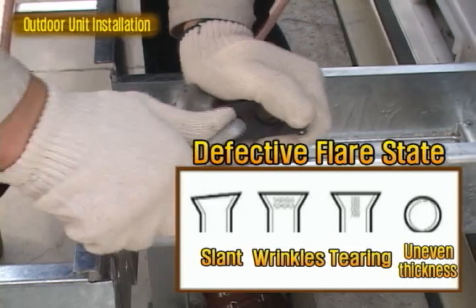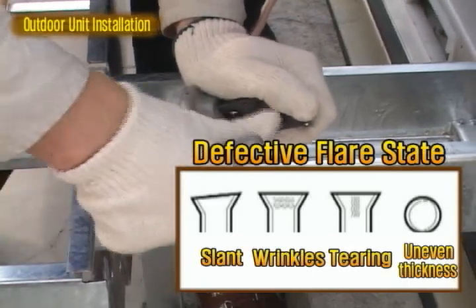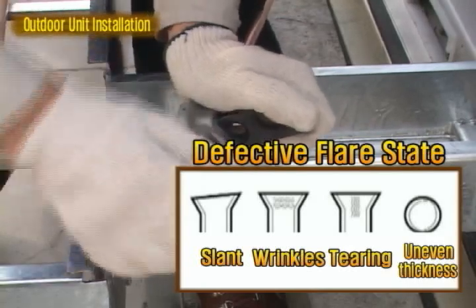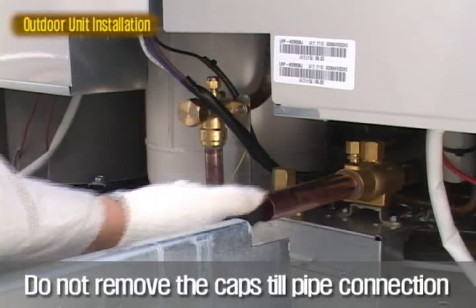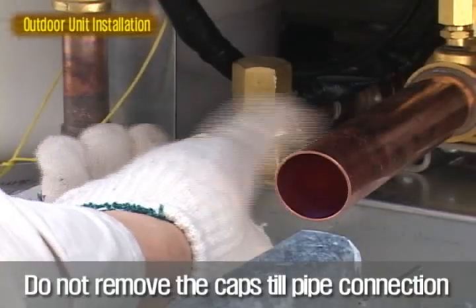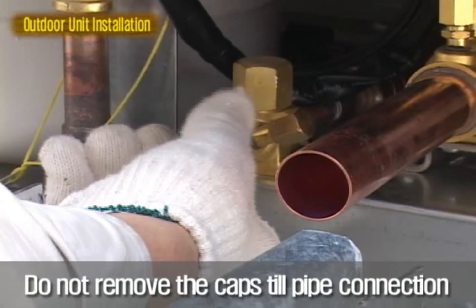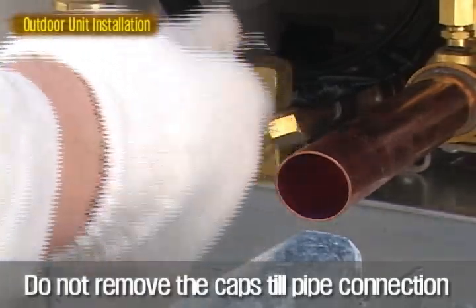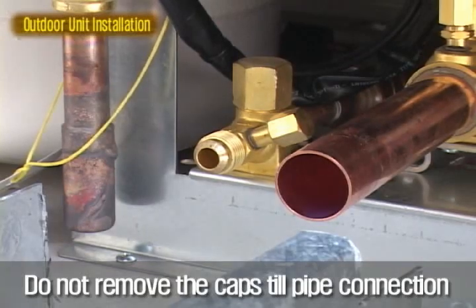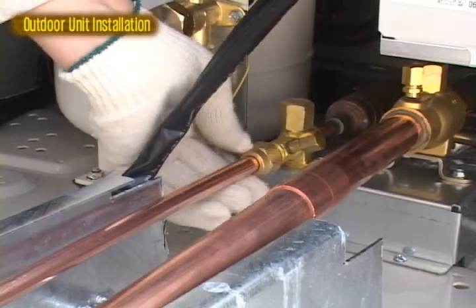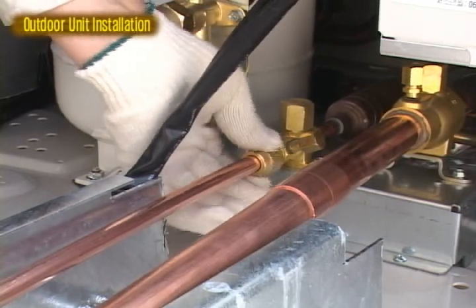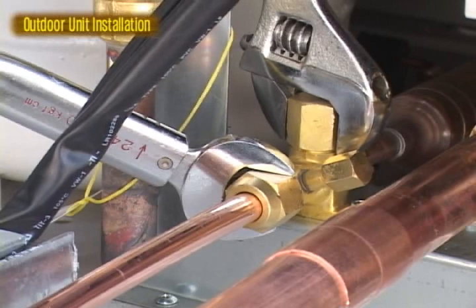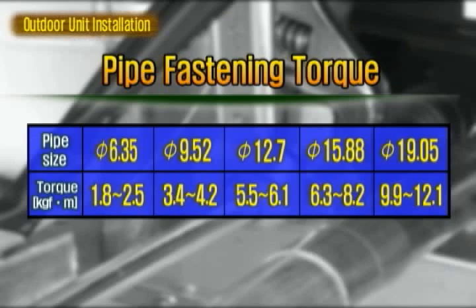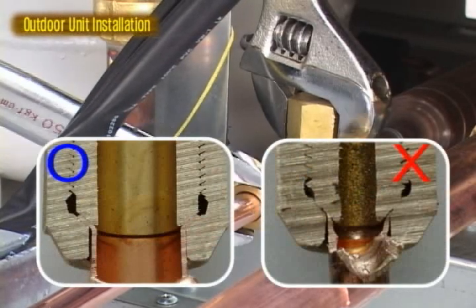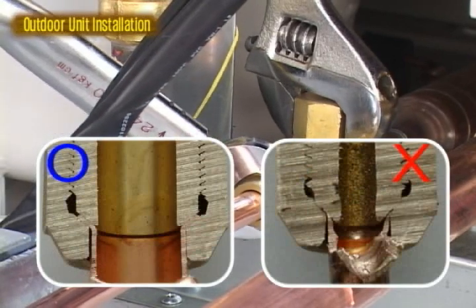Flare contact should be tight and accurate, otherwise leakage problems can occur from the flared part. Do not remove the nut and cap from the service valve and tube until just before the fitting. Earlier removal will cause troubles like allowing foreign materials into the pipes. Line up the branch distributor unit socket and flare center close to each other and join with hands before tightening it with the torque wrench to the given specification. In case the torque applied is not within the specification range, leakage can occur.